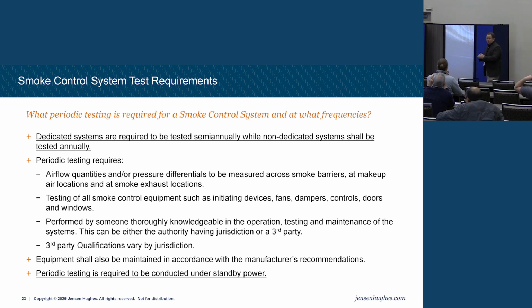Remember I said a stairwell pressurization system or an atrium system, there may be a differential pressure required across the threshold of the door. That needs to be tested as part of the periodic testing requirements. Testing of all smoke control equipment, initiating devices, the fans, the dampers, the controls, the windows, all of that stuff is considered part of the semi-annual or annual for non-dedicated. Backwards. Semi-annual for dedicated, annual for non-dedicated.